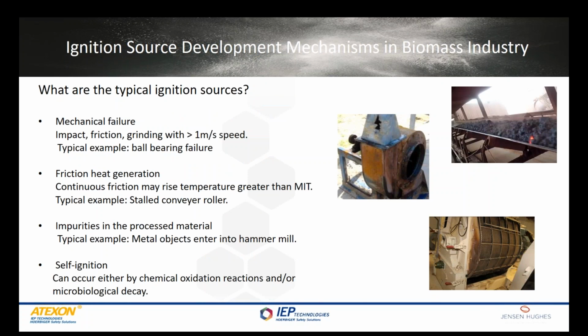It is known that there are 14 different, or 13 different, ignition sources that can ignite dust explosion. Martin had a longer list in his presentation, but I am concentrating here on 4 of them, which are the most interesting from a spark detection and extinguishing point of view. The first, mechanical failure, is a very common cause of fire or explosion accident. Mechanical movement greater than 1 meter per second can produce mechanical sparks or spark streams. Typical example is ball bearing failure of dust extraction fan, especially if the fan is located at dirty side of the dust collector.